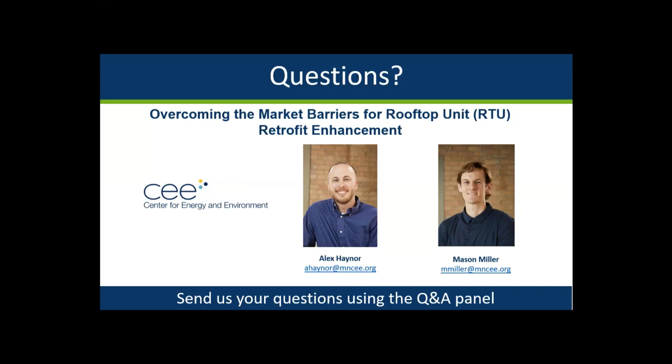RTUs can have interesting interactions with one another, and small set point changes to specific units can have a significant impact on how much a unit runs. So many of the units for this particular field site really did not show significant cooling runtime. This is something we found in the project as well as past research: RTUs that serve the same space type, which for this field site was an office space, a large open space, operate differently based on the thermostat set points. Because of this, some of the units just simply won't run a lot, and then others will run more. So for units that rarely run, a few cooling events in that pre-period can have a large impact on the calculations and results.